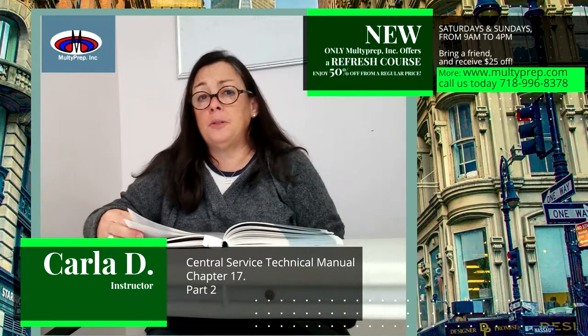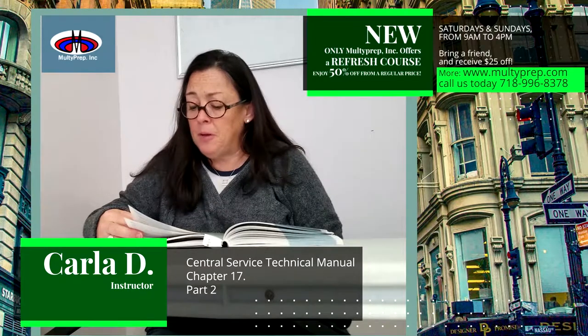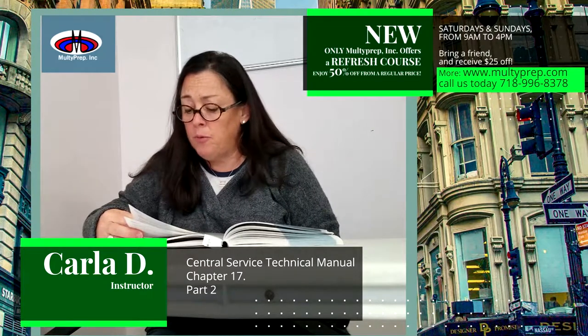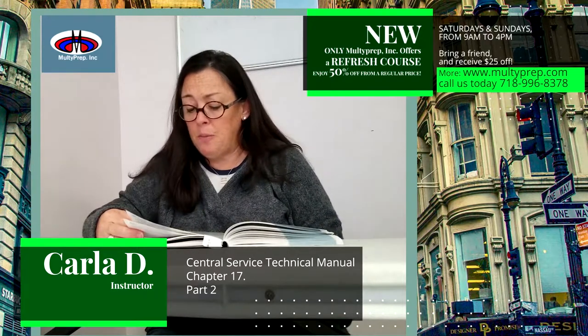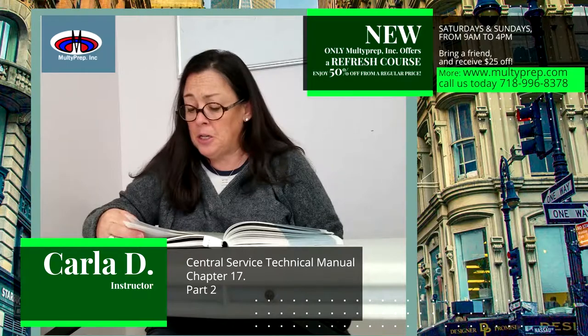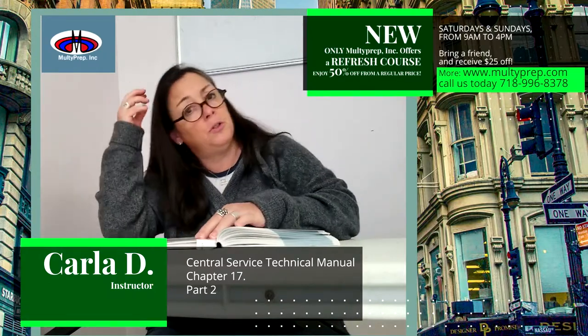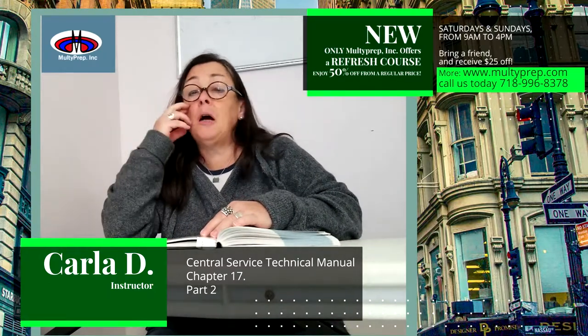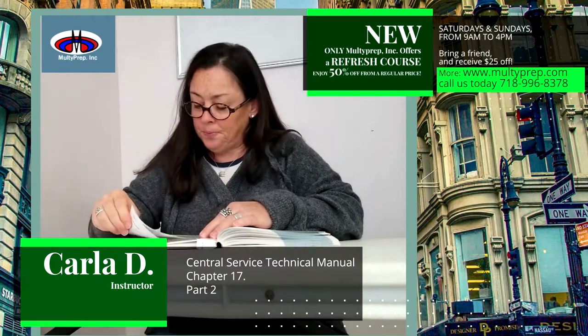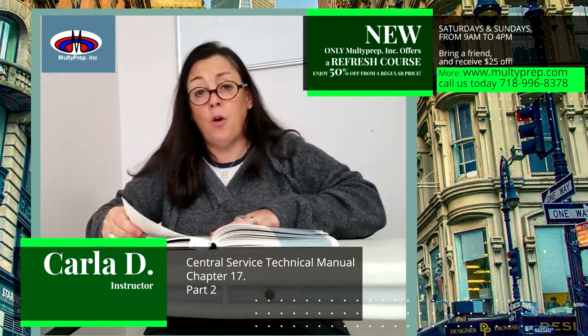Multiple cycle testing. Some dynamic air removal and immediate use steam sterilizers have the ability to operate in either a dynamic air removal mode or a gravity mode. If the sterilizer is used in both sterilization methods, then BI and PCD testing must be done at least weekly, preferably daily, in both modes. Refer to ANSI AAMI ST79 and to the sterilizer manufacturer's instructions for use for specific details. Tabletop steam sterilizers, commonly known as autoclaves.